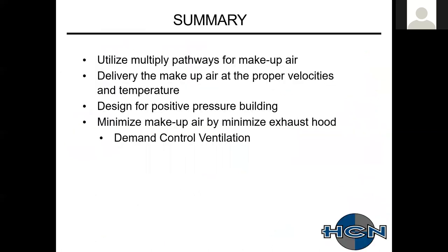So to summarize what we talked about today, the major thing I wanted to say is we definitely want to utilize transfer air as much as we possibly can. You're already heating and cooling that ventilated air, so if we can utilize that air, we take that away from the dedicated makeup air that we have to provide. Code requires the overall building to be slightly positive. Near the hood system, we definitely want to be negative because we don't want any of that effluent smoke getting into your patrons and diners. So the big thing is our best bet is always to try to utilize multiple sources of makeup air as best we possibly can, given the design constraints of the building and what we have to deal with.